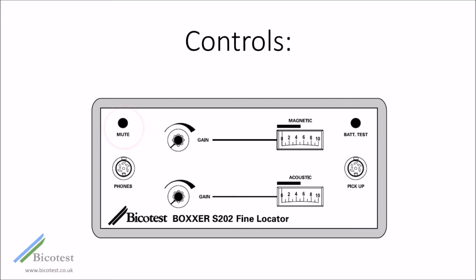Mute button. Black push button switch disables headphones when pressed, i.e. no acoustic signal to the headphones while depressed. This switch enables the acoustic pickup to be moved for signal comparison purposes without adjusting the gain control, thus removing the discomfort of loud acoustic signals on the headphones when gain is high.